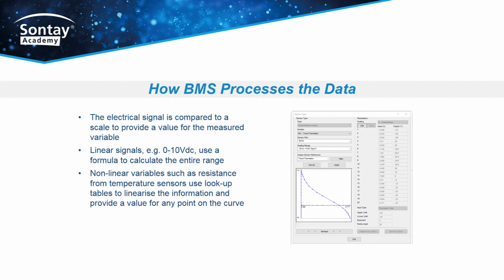Non-linear signals, such as those derived from a thermistor, need to be linearized. Linearization is the process of selecting multiple points on the temperature resistance curve and providing a coefficient for each segment, corresponding to the steepness of that part of the curve. These are often called lookup tables.